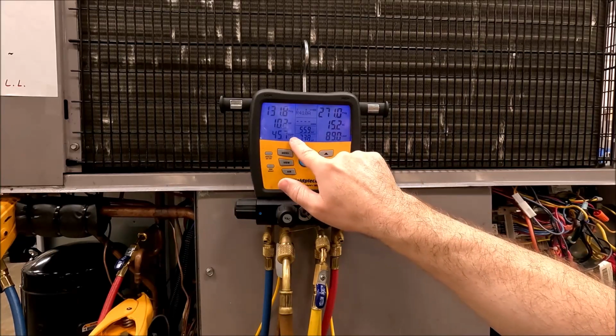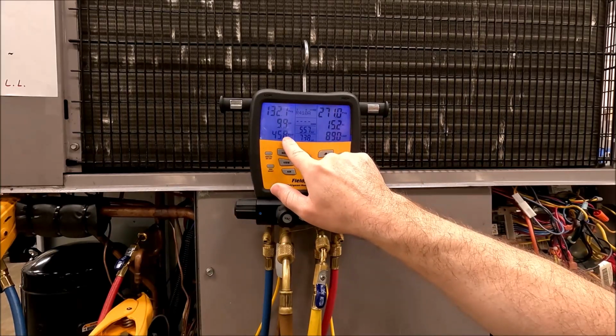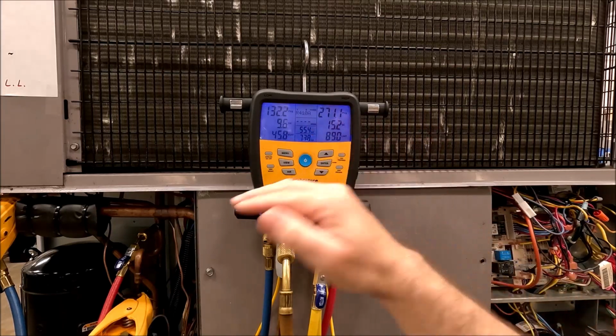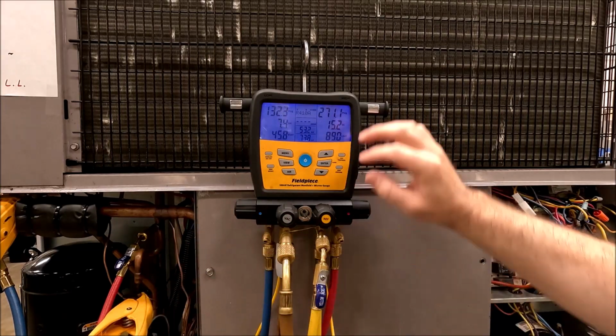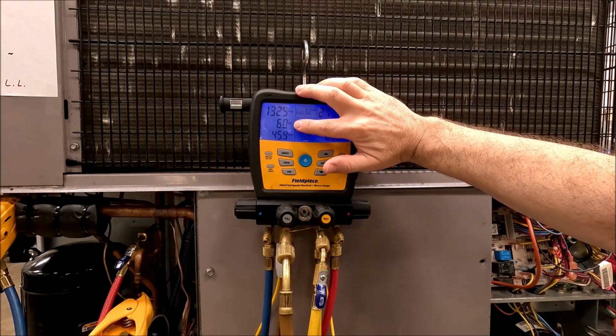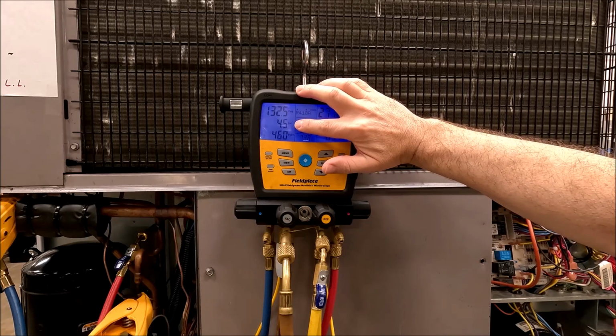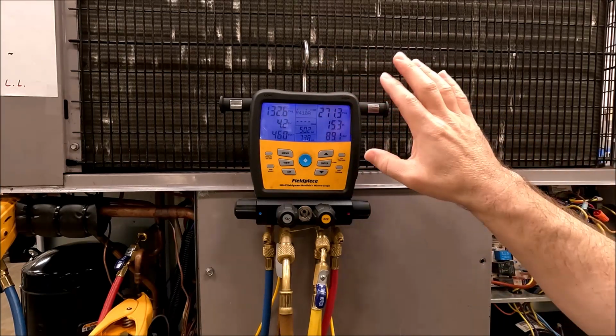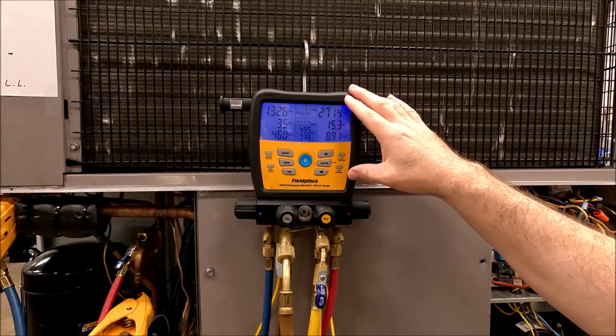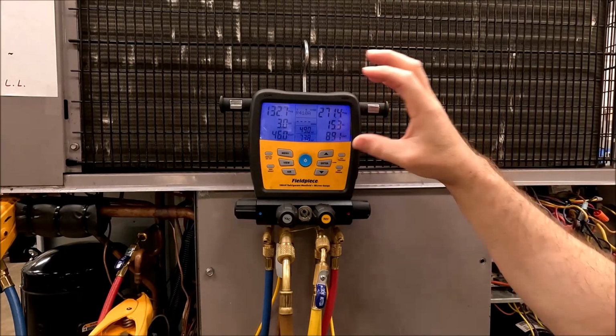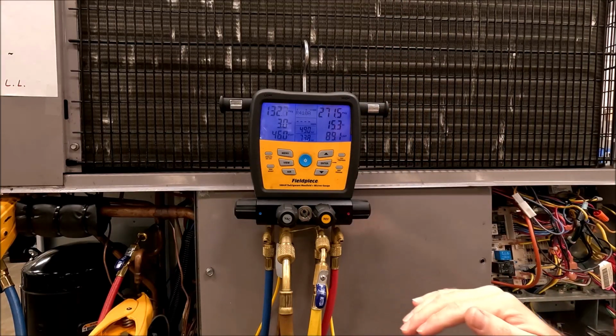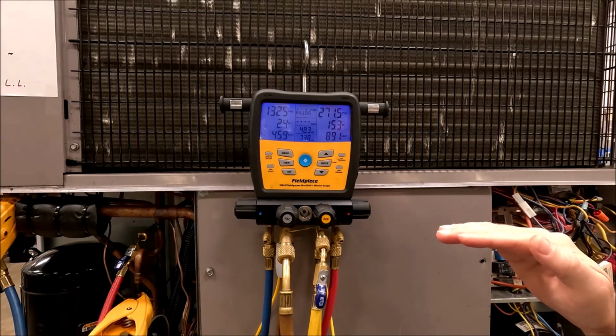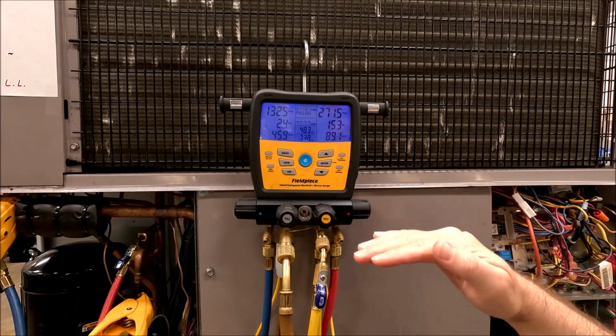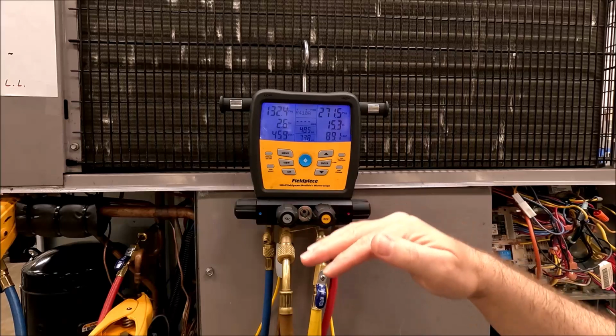So it says here VSAT. This is your vapor saturation. That's a reference to your evaporator. Okay. This middle number here says SH, superheat, and you can watch it go up and down. This is to me the beauty of the digital gauge. I can see small changes, and what you'll notice is our numbers don't really stay the same. They kind of have a little roll to them, a little flow.